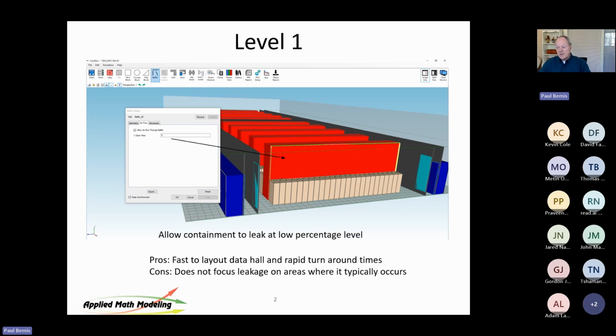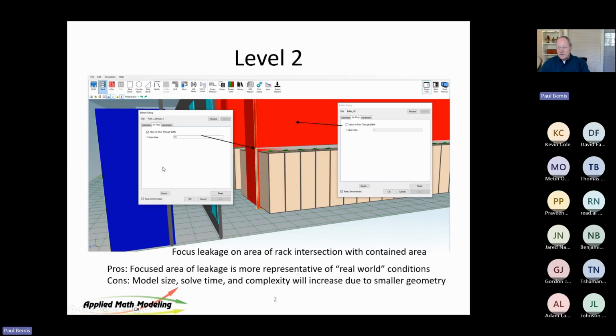In this case, what we're doing is we're letting the material leak. It's called porous media in fluids terms or fluids talk. Here I'm letting it leak at 5%, which is the default number on the baffle for our software CoolSim. So we let it leak at 5%, air goes in. And it's a large surface. So a percentage of a large surface is a fairly large number. So level one's okay. It's quick. It's easy. I tend not to use it anymore. We used it originally for quite a period of time. It worked well. But as you crank these things up, I tend to go for a different level.